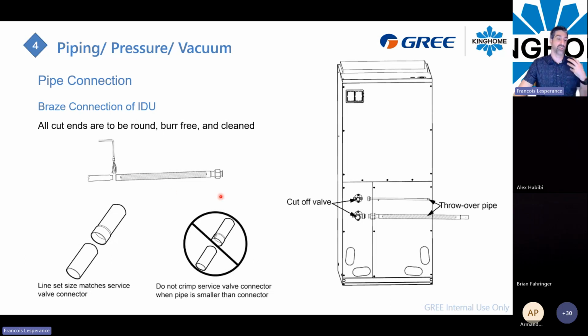So if you struggle to make the bend correctly with the piping, you can use those extensions, already flared, and you can braze them. But just remember that if you need to braze, always use your nitrogen to make sure you will not create oxide inside of the pipe that, at a certain point, will block the TXV.